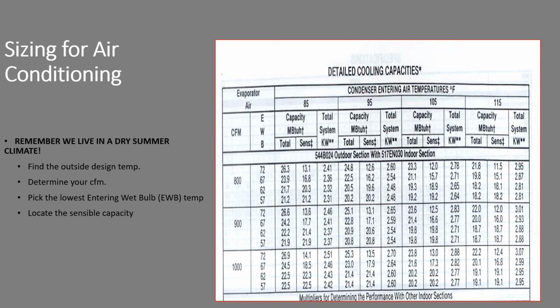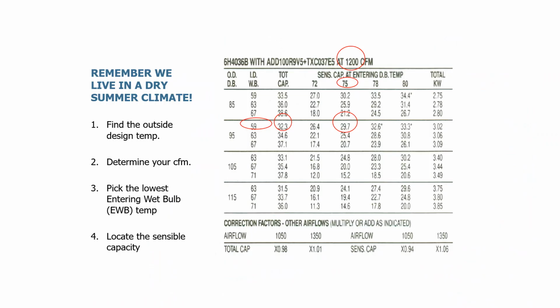Now we have to figure out what is going to be our best air conditioner to match the load of the house. Unfortunately, every manufacturer does these detailed capacity tables just a little bit different, making our lives complicated. But all of them tend to have at least this information, and the basic project is to find the outside design temperature. In this case, we're going to pick 95 degrees. That's pretty realistic. Determine your CFM.